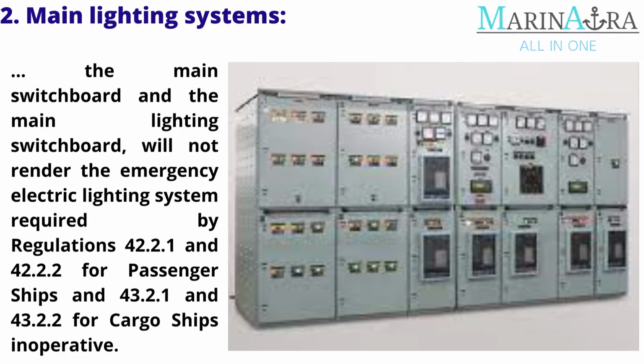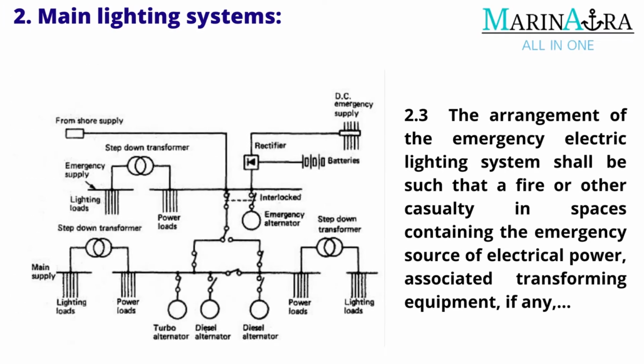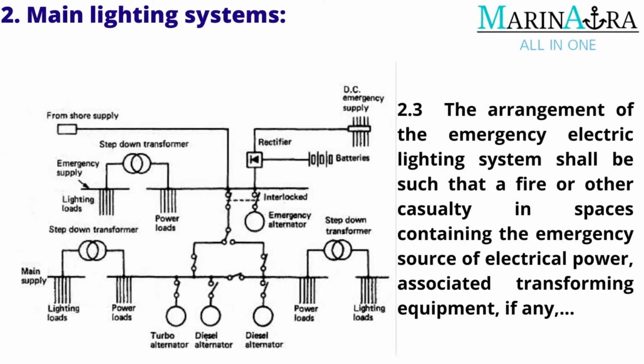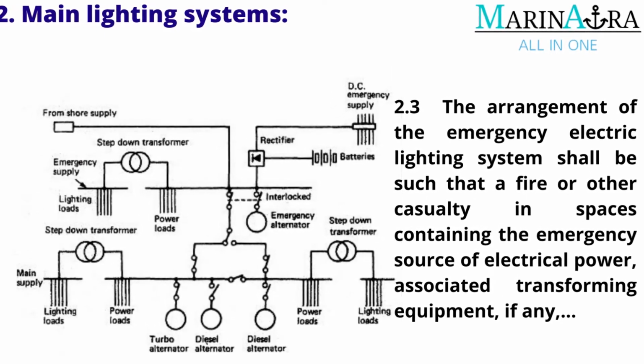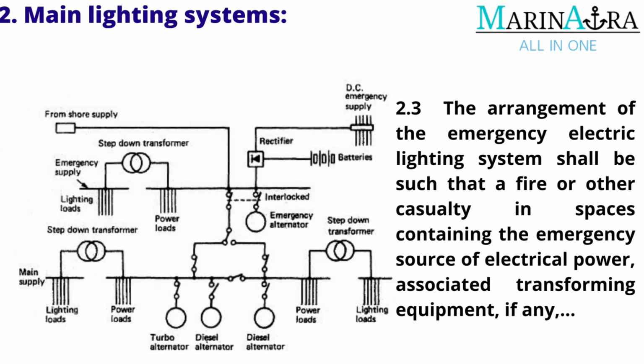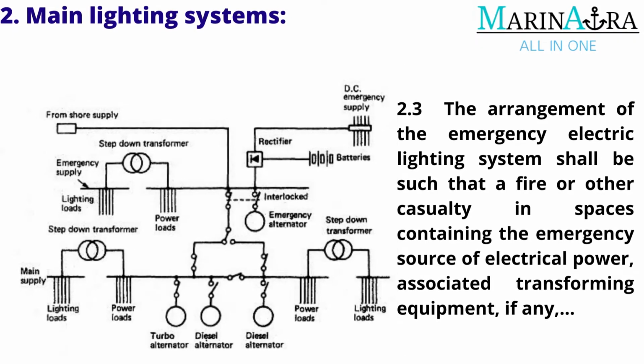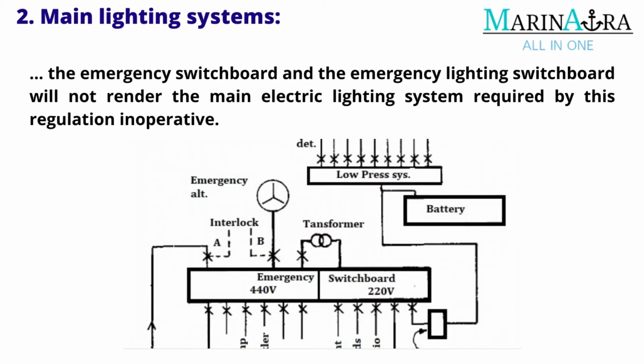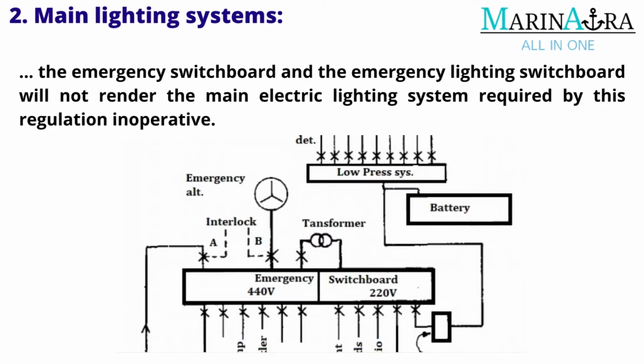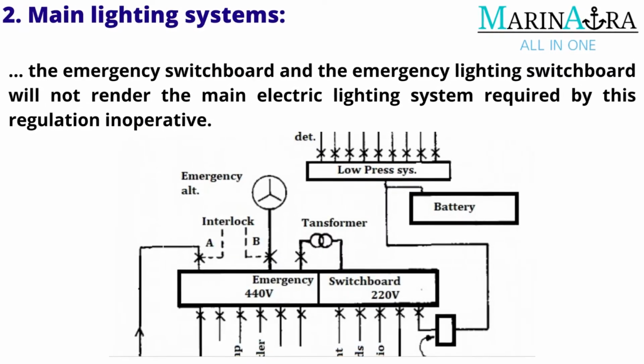for cargo ships inoperative. The arrangement of the emergency electric lighting system shall be such that a fire or other casualty in spaces containing the emergency source of electrical power, associated transforming equipment, if any, the emergency switchboard and the emergency lighting switchboard will not render the main electric lighting system required by this regulation inoperative.